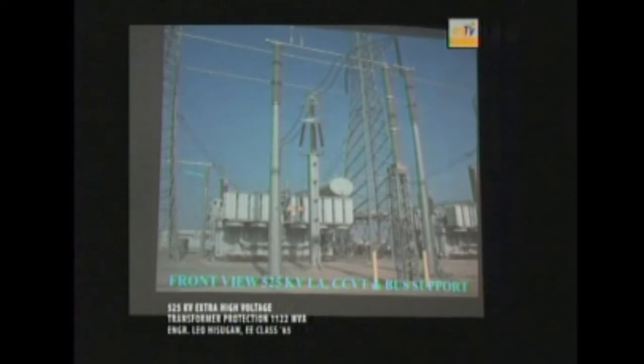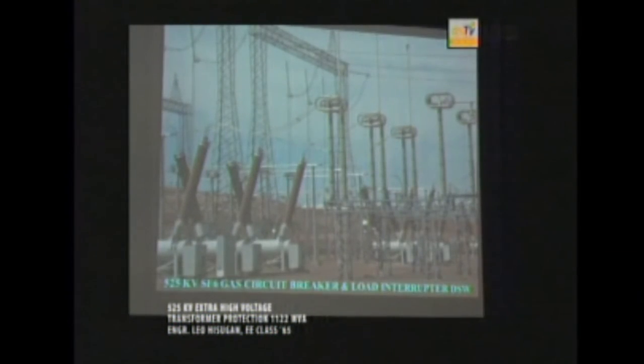Another view of the transformer here. This is the lightning arrestor, and this is your CCVT. Your CCVT for the volts per hertz protection is, for example, using 115 volts line to neutral. The CCVT normally has 2 windings, the X winding and the Y winding. You can connect the X winding to 120 volts, for example, and the Y winding you can connect to the circuit breaker, the SF6 gas circuit breaker for each transformer.